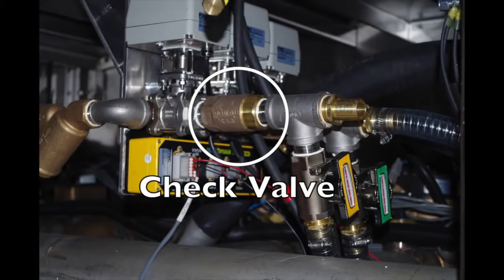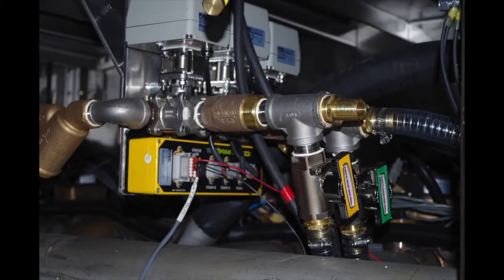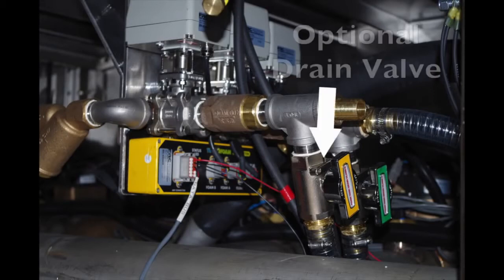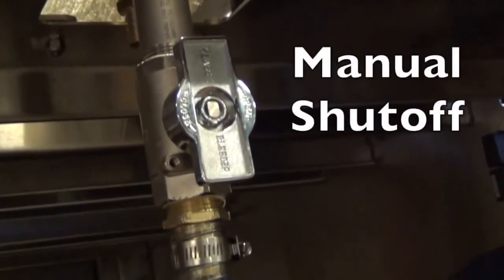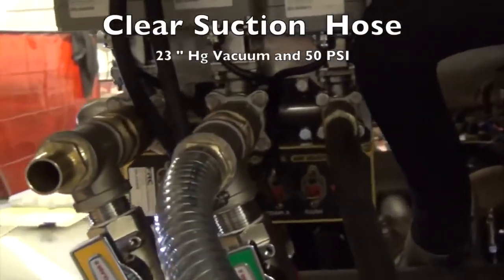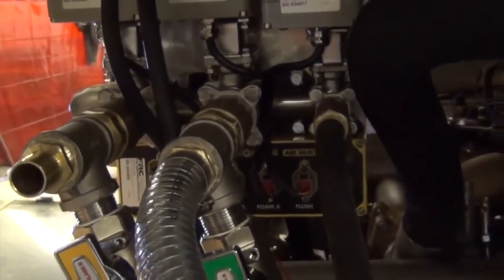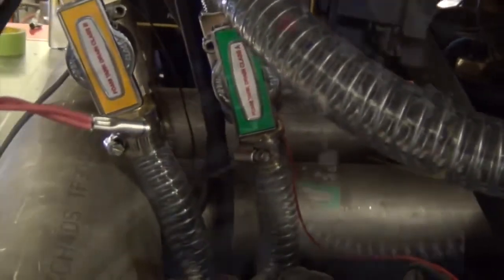If possible, mount the foam tank check valves directly to the foam valves on the selector assembly. If this is not possible, all plumbing between the selector assembly and foam tank check valve should be as short as possible and rated for at least 500 psi. In this picture, you see an optional foam concentrate drain valve and hose. A manual shutoff valve must be installed between the foam tanks and check valves on the valve selector assembly. The foam concentrate clear suction hose must be rated for at least 23 inches of mercury vacuum and 50 psi.